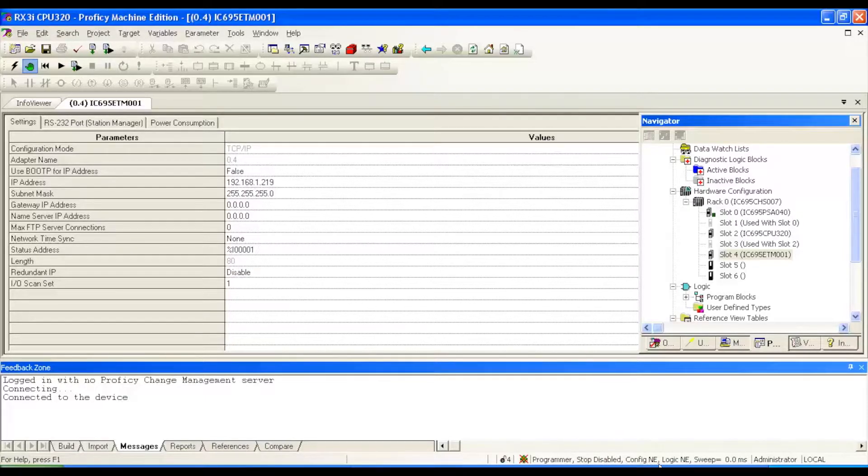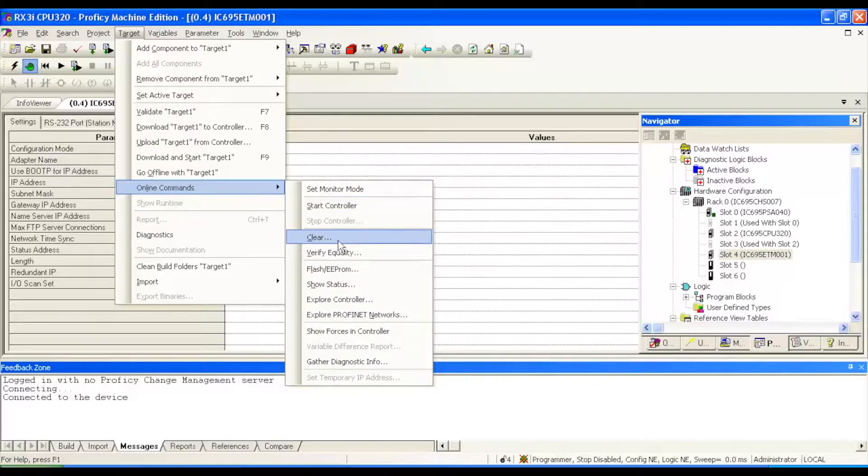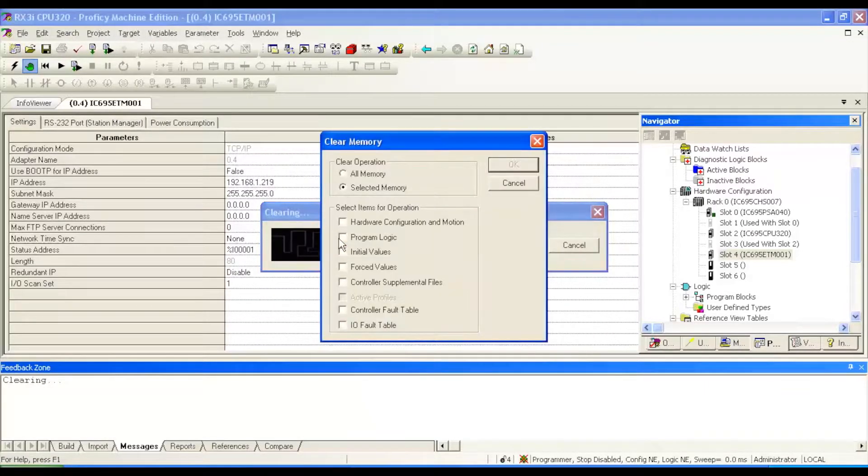Same thing as all the processor tests. We're going to go to target, online commands, and we're going to clear controller and IO fault tables. This will keep us from getting hung up throughout the download process.